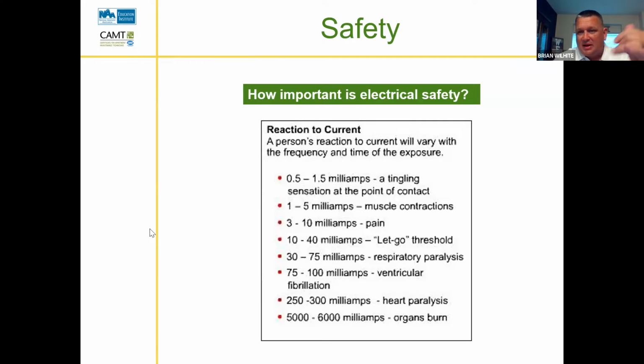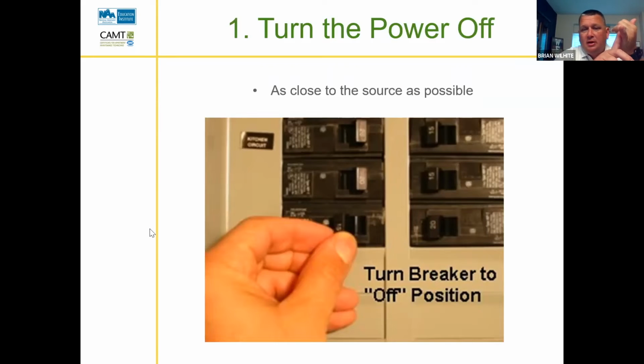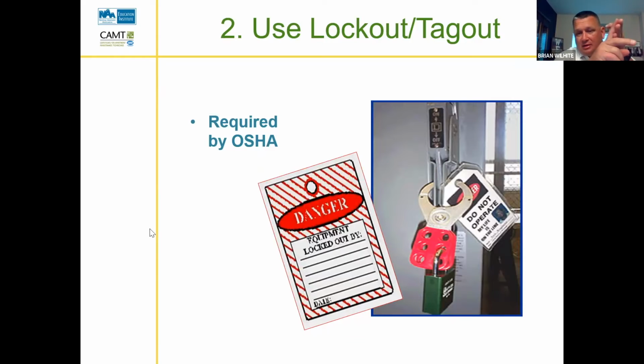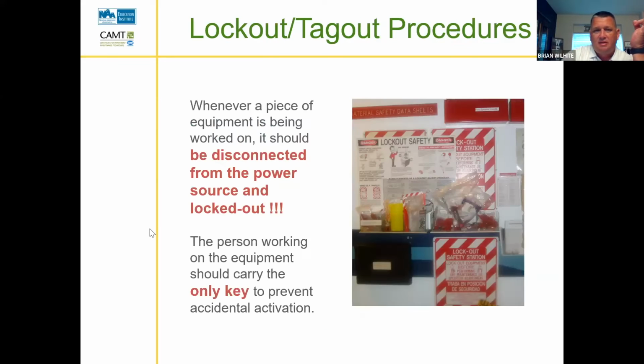There are a few things we need to pay attention to. One, when we're working with electricity, we always need to wear our PPEs. We always need to turn the power off as close to the source as possible. We need to use our lockout, tagout procedures, which we'll talk about in a minute. And there's a word I'm going to beat into our heads over and over again that starts with a V. Does anybody know what that word is? Verify. Yeah, we want to verify every time that the power is off.